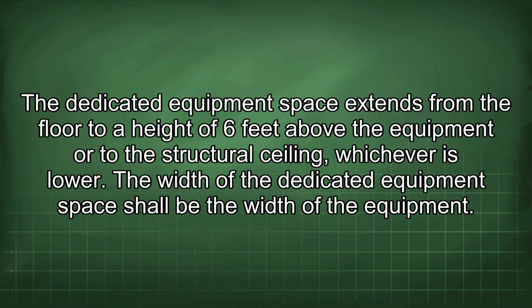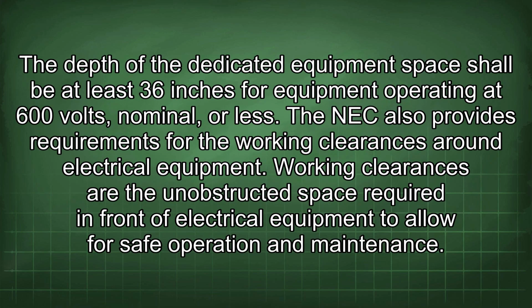The dedicated equipment space extends from the floor to a height of 6 feet above the equipment or to the structural ceiling, whichever is lower. The width of the dedicated equipment space shall be the width of the equipment. The depth of the dedicated equipment space shall be at least 36 inches for equipment operating at 600 volts, nominal or less.